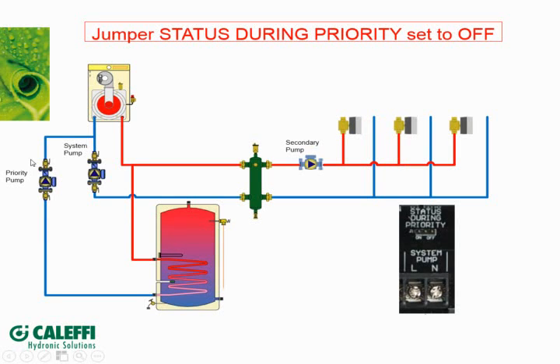So when there's a priority call, this pump fires, the boiler goes to high temp, and you load up your indirect. Once it's done, the priority pump shuts down, and then if there's any call for heat by any of these zone valves, the control can fire the secondary pump and the system pump. And that'll also post-purge on that one, right?